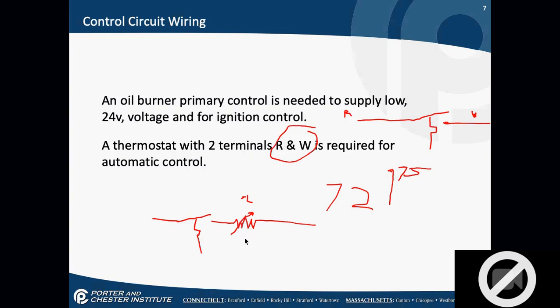So our heating anticipator actually creates a little bit of heat when this thermostat is calling for heat. Okay? And it puts a little bit of heat onto the sensing mechanism in that thermostat. And it says, okay, the thermostat now thinks it's 72 degrees, but it's actually 70, so that residual heat I'm going to blow out of the furnace is going to warm my house that extra 2 degrees to get it to 72 degrees.